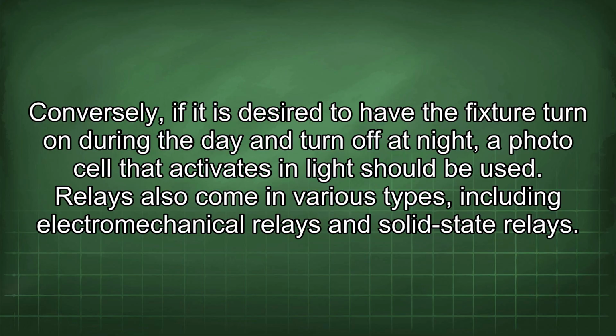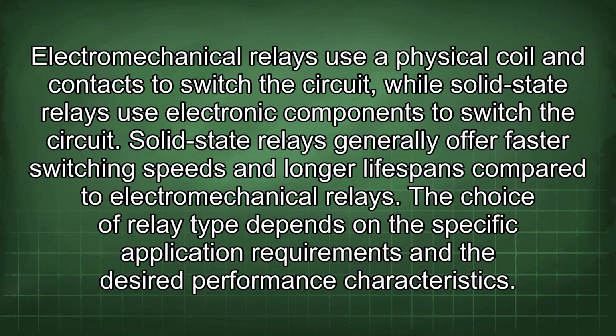Relays also come in various types, including electromechanical relays and solid-state relays. Electromechanical relays use a physical coil and contacts to switch the circuit, while solid-state relays use electronic components to switch the circuit. Solid-state relays generally offer faster switching speeds and longer lifespans compared to electromechanical relays. The choice of relay type depends on the specific application requirements and the desired performance characteristics.